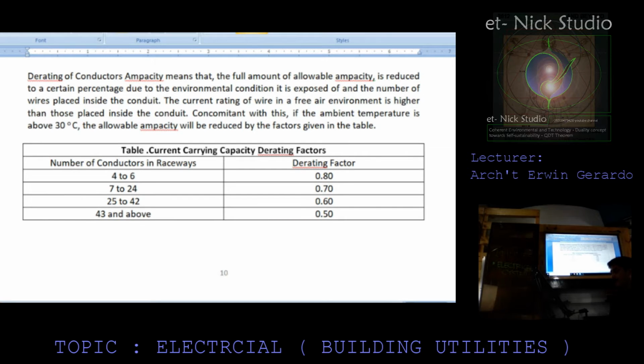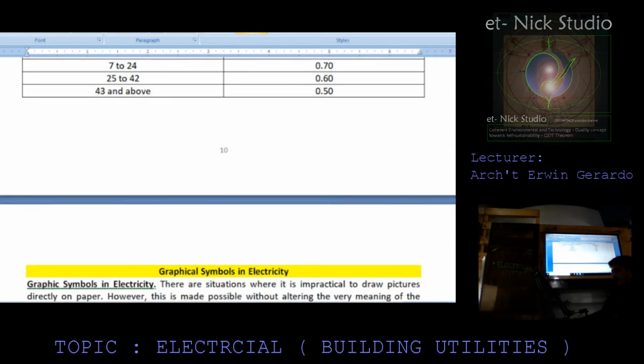Number of conductors inside the raceway: from 4 to 6, the derating factor is 0.80. From 7 to 24, the derating factor is 0.70. From 25 to 42, the derating factor is 0.60. 43 and above, the derating factor is 0.50.